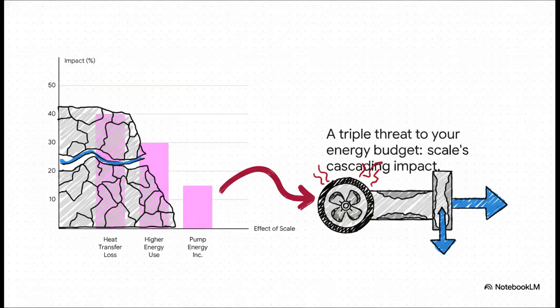First up, that layer of scale kills your heat transfer. We're talking a loss of up to 40%. So what happens next? Your chiller's compressor has to go into overdrive to make up for it, pushing its energy use up by 15, maybe even 30%.